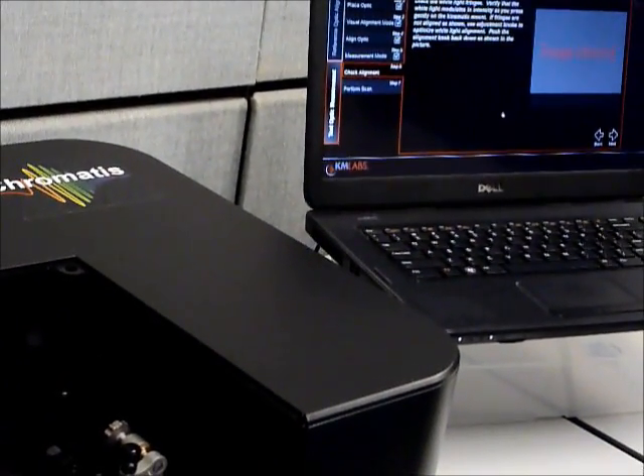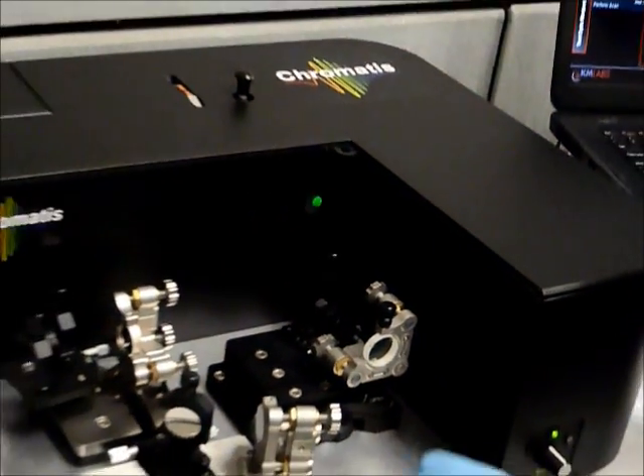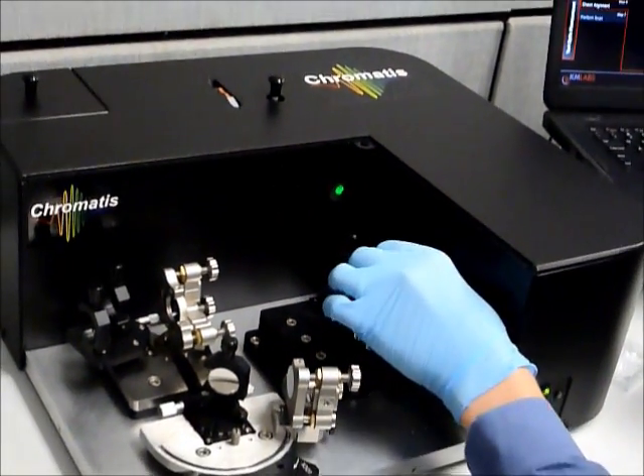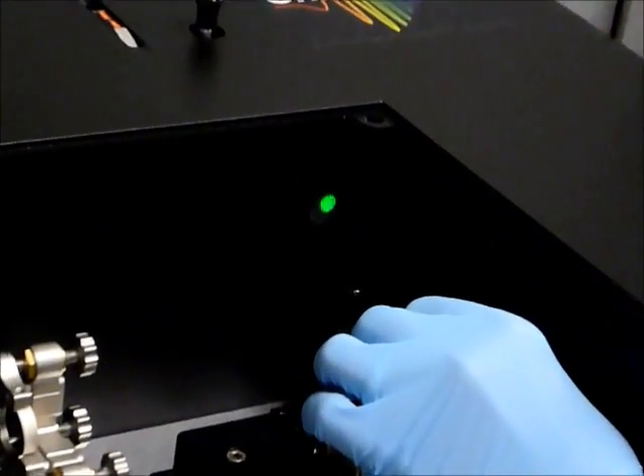And once it is done with this, you can recheck the fringes to see if you maintained good alignment and make any last adjustments. And then we're ready to make a measurement.